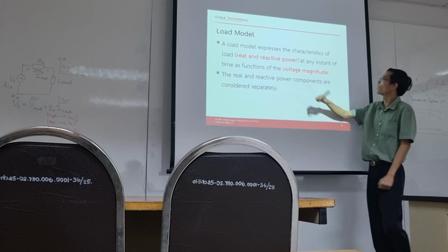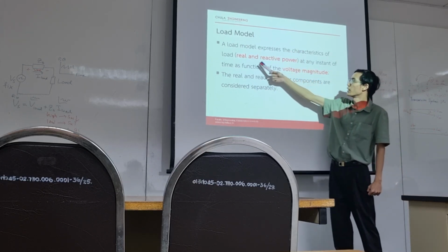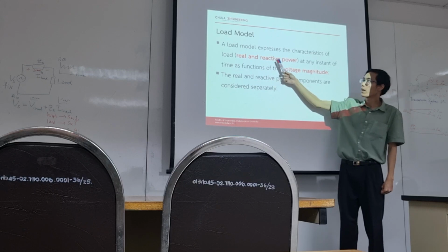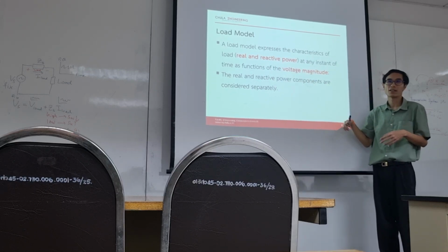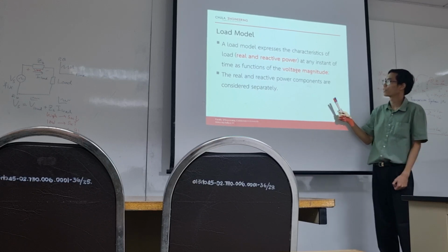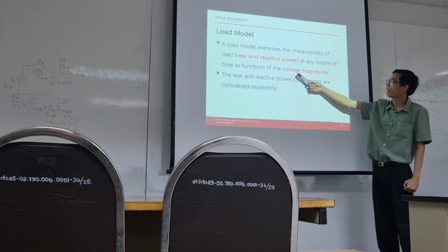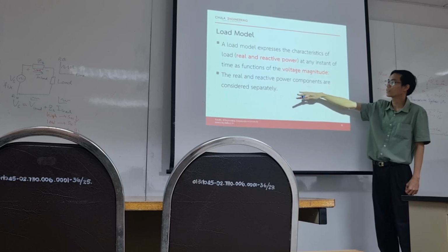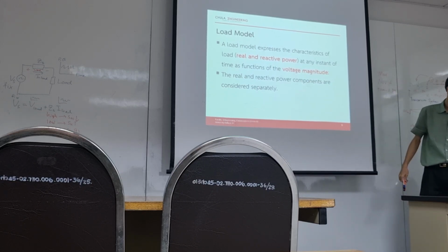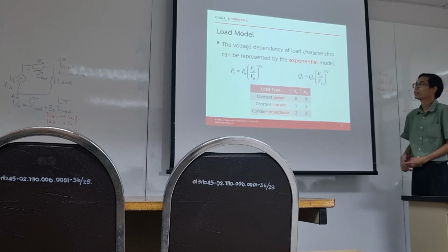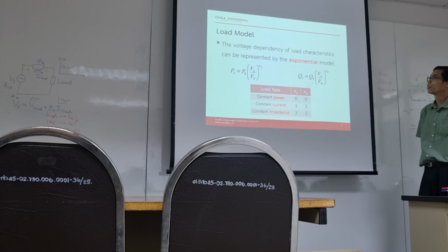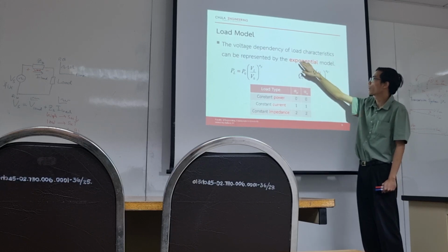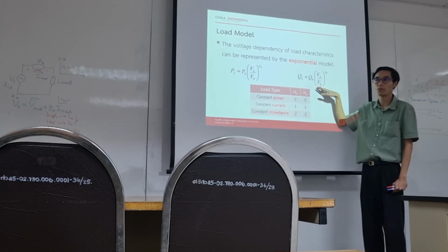Okay, when we talk about the load characteristic, it means real and reactive power of the load. The real and reactive power of the load can vary, right, according to your usage. So it can vary as a function of voltage magnitude. We can consider real and reactive power separately. So this is the load model. The voltage dependency of the load characteristic can be represented by this exponential model.